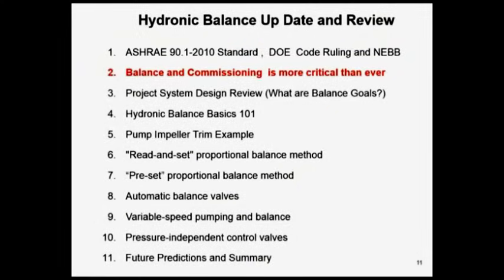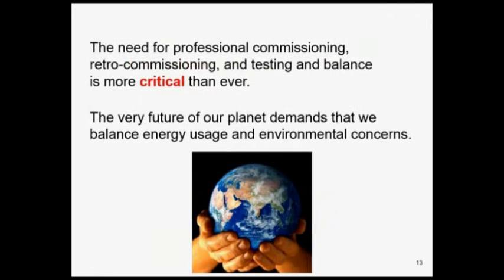How about balancing and commissioning? Why do we keep talking about balance and energy? It's real simple: it's more critical than it ever has been before. If you look at ASHRAE's drive with 62 and 90.1, 90.1 is an energy code trying to drive the efficiency to the bare minimum. 62 is IAQ. They're trying to make sure the air is fresh, clean, and comfortable. So the two kind of go against each other a little bit, because on one side you're trying to make sure you have as much air as you need, which takes more energy and is comfortable. On the other side, energy. So you've got to balance the two. You've got to commission systems to make sure you don't have too much air, to make sure you have the right amount of air, and to make sure they're balanced.